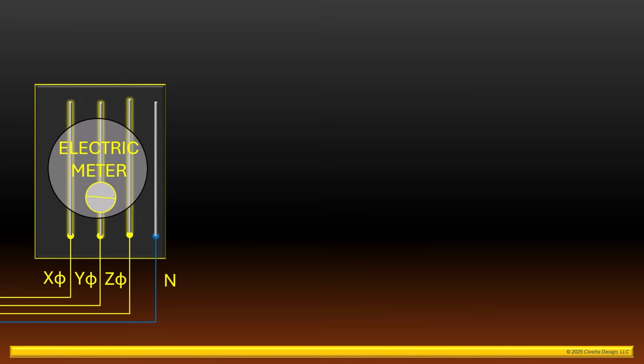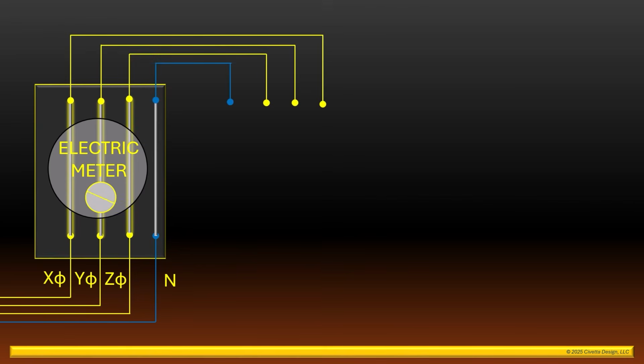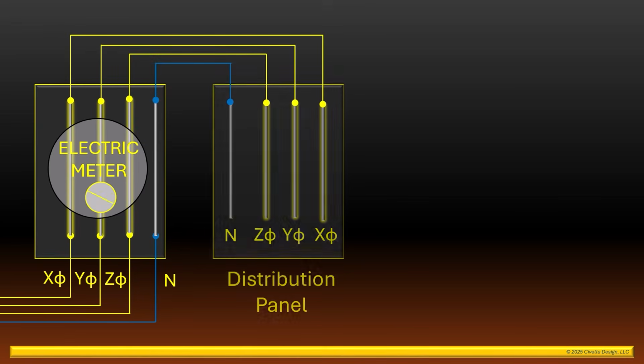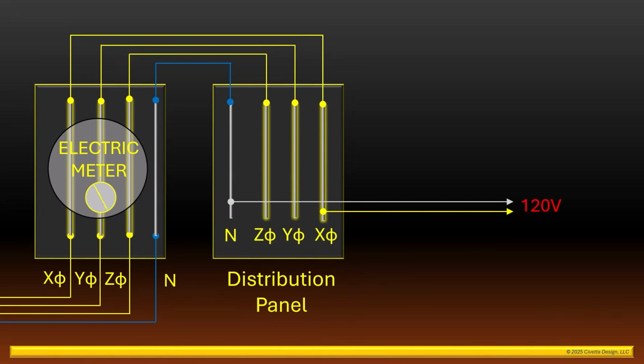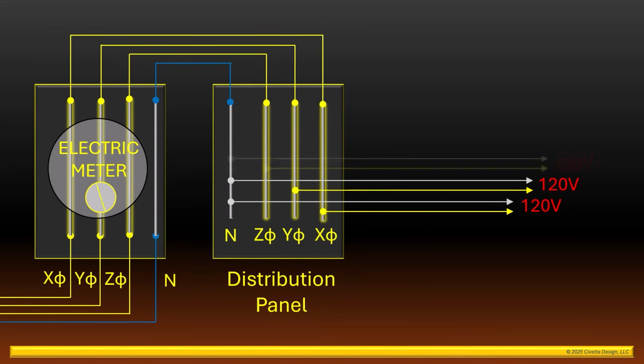Bus bars carry the power through the meter so the utility can monitor power consumption. Another set of four conductors carry the power to the distribution panel. Now, a Y-connected transformer bank can provide 120-volt power by using the X phase and the neutral, the Y phase and the neutral, and also the Z phase and the neutral.